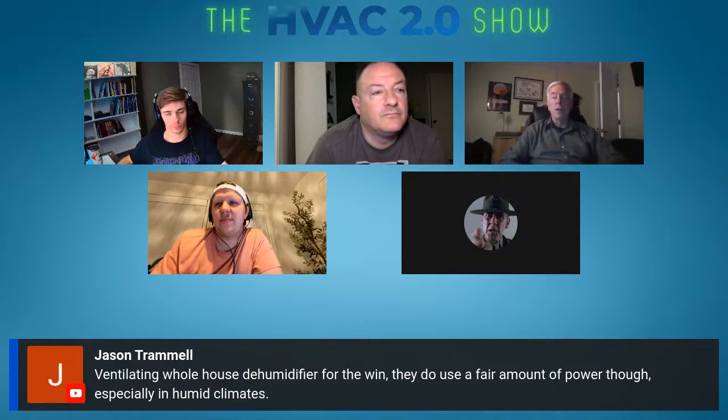Dehumidifiers should principally be for low load times. If your air conditioner is properly sized and adjusted, it should be removing humidity during normal run times. But shoulder seasons, evenings, rain conditions, when the air conditioner isn't running, that's when the dehumidifier should be helping out in order to bring things back into the desired environment. Not being fully reliant. That's a good point.